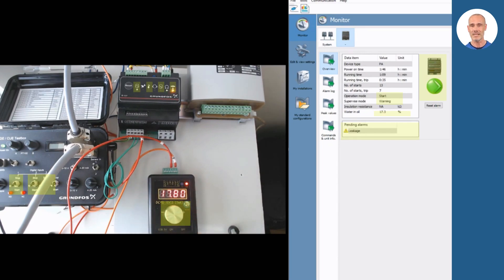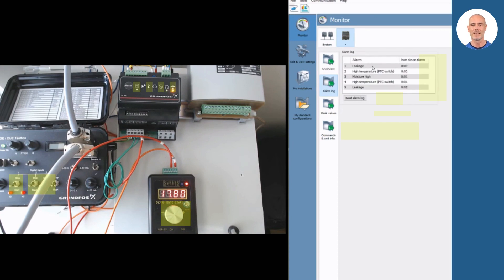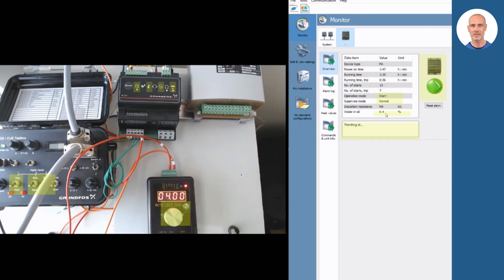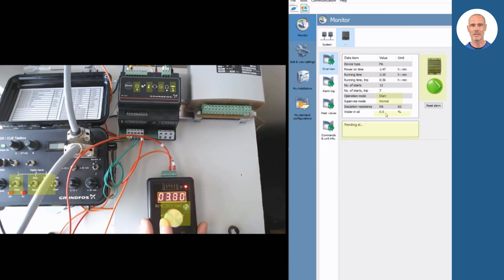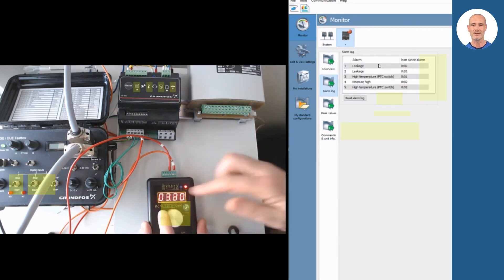In the PC tool you could appreciate how the measurement percentage increases, based on the analog signal. Please remember that IO-113 will open the alarm and the warning physical outputs when it happens. Also remember that IO-113 will not measure if the pump running status is not active.